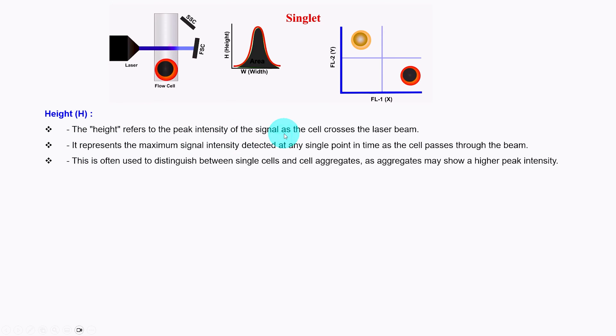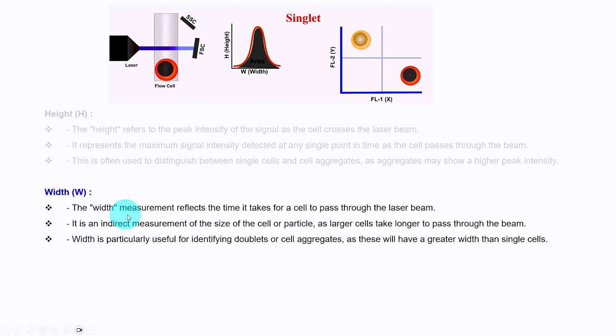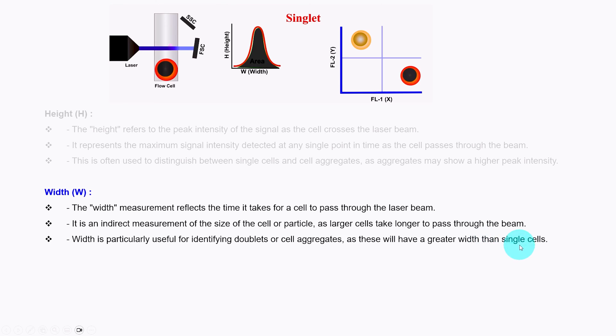The height refers to the peak intensity of the signal as the cell crosses the laser beam. It represents the maximum signal intensity detected at any single point in time as the cell passes through the beam. This is often used to distinguish between single cells and cell aggregates, as aggregates may show higher peak intensities. Width reflects the time it takes for a cell to pass through the laser beam and is an indirect measurement of cell size. Width is particularly useful for identifying doublets or cell aggregates, as these will have a greater width than single cells.